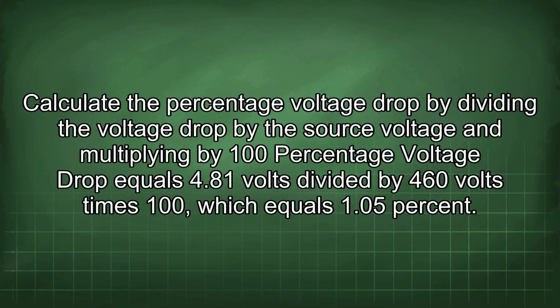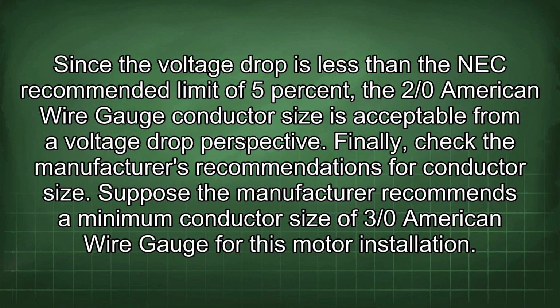Percentage voltage drop equals 4.81 volts divided by 460 volts times 100, which equals 1.05%. Since the voltage drop is less than the NEC recommended limit of 5%, the 2/0 American wire gauge conductor size is acceptable from a voltage drop perspective.